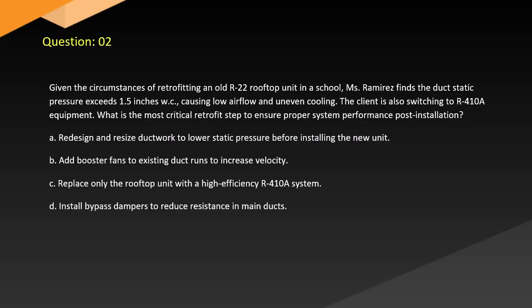Question 2. Given the circumstances of retrofitting an old R22 rooftop unit in a school, Ramirez finds the duct static pressure exceeds 1.5 inches W.C., causing low airflow and uneven cooling. The client is also switching to R410A equipment. What is the most critical retrofit step to ensure proper system performance post-installation?